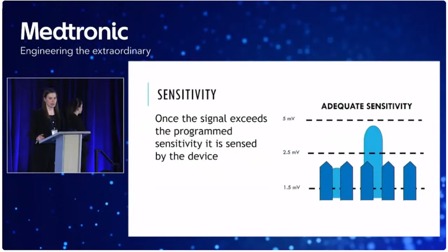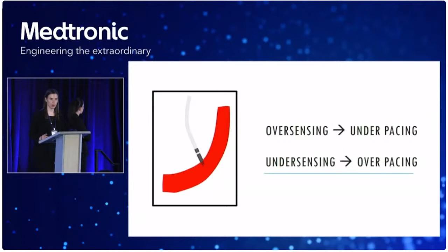And our needs in a pacemaker are different than our needs in a defibrillator. In a defibrillator, we want to see ventricular fibrillation, which can be quite small. In a pacemaker, we want it to be able to see P waves and R waves. Well, what about problems with sensing? So if we have an over-sensing problem, that can lead to under-pacing. If we have an under-sensing problem, that can lead to over-pacing, and that can lead to calls in the middle of the night when you're on call. So if you're the cardiology fellow or the EP fellow, things on telemetry, changes on electrocardiograms can generate consults, can generate phone calls for you. So it's important to understand them so that you can then move forward to troubleshooting.